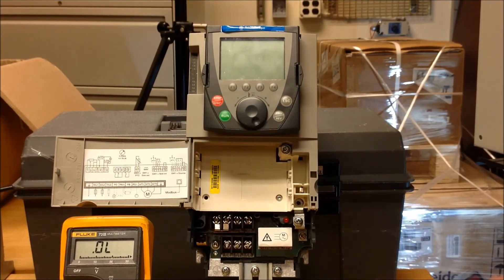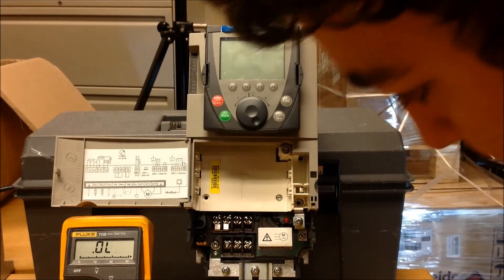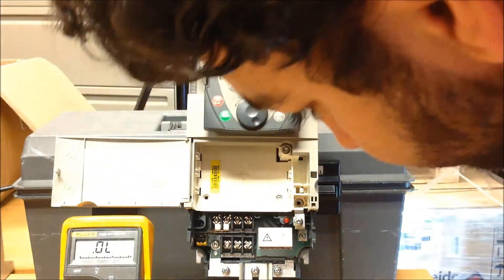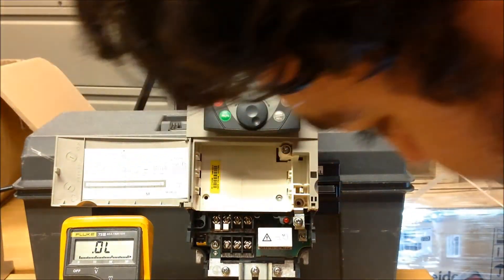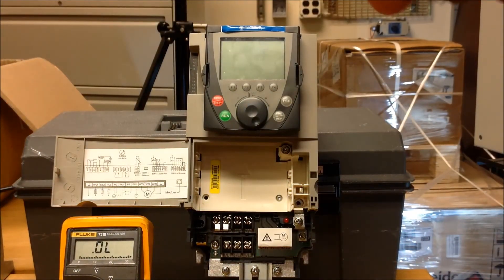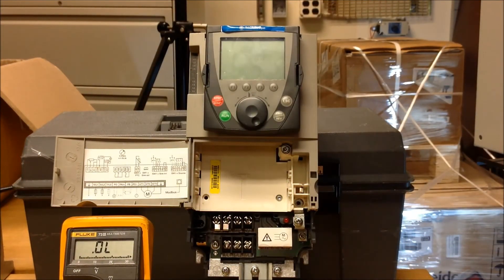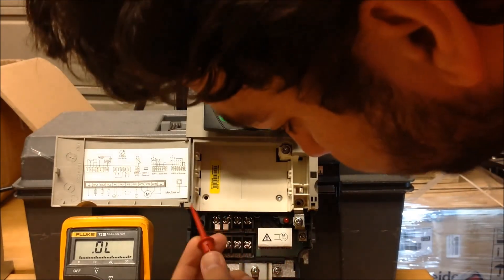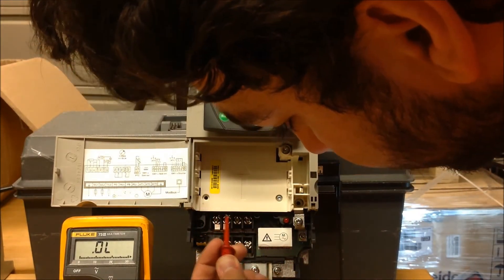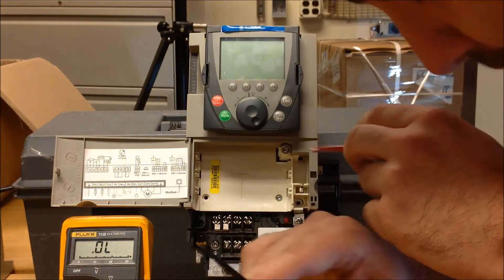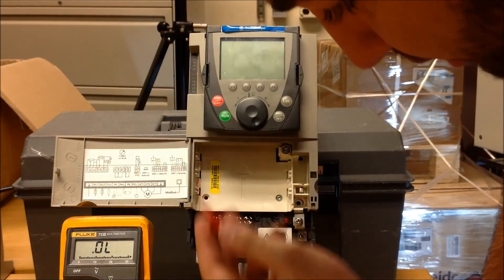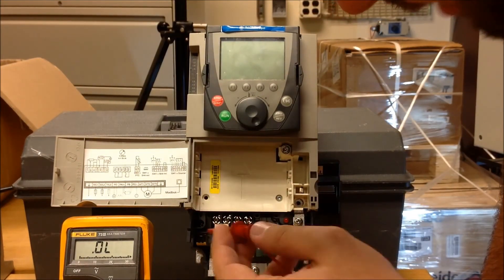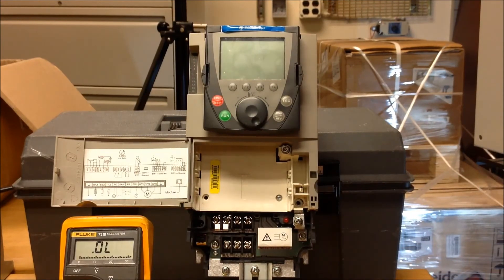Let's go and measure the output side now to T1, 2, and 3. To do that, you'll have to make sure that you don't have any power here, but it's the exact same measurement, with the only difference being that you'll go from your PA plus and PC minus with both directions to T1, T2, and T3 of your drive.